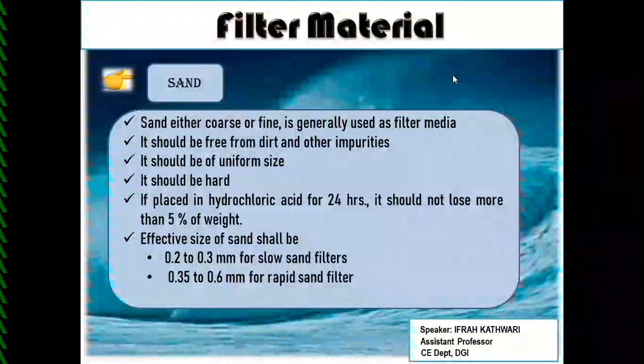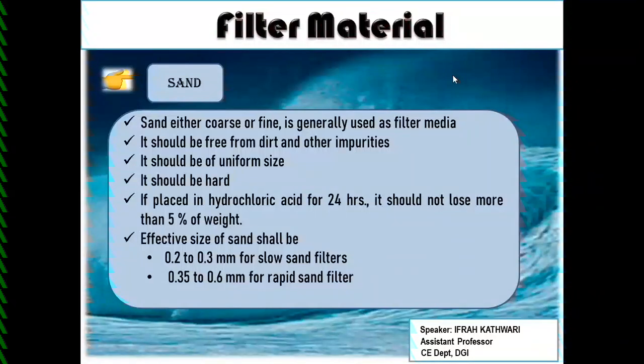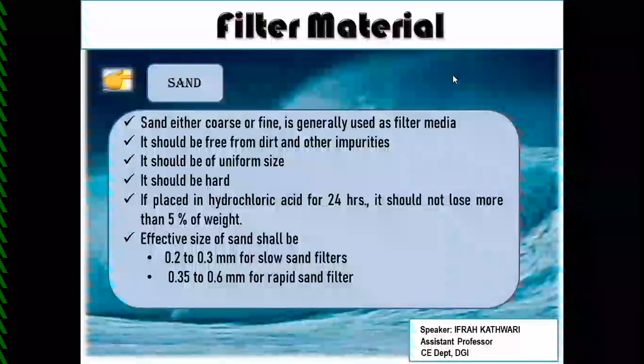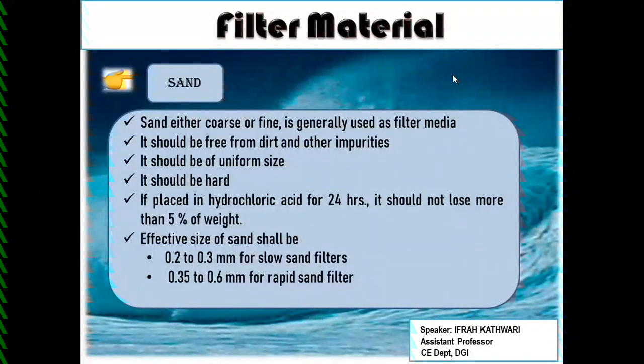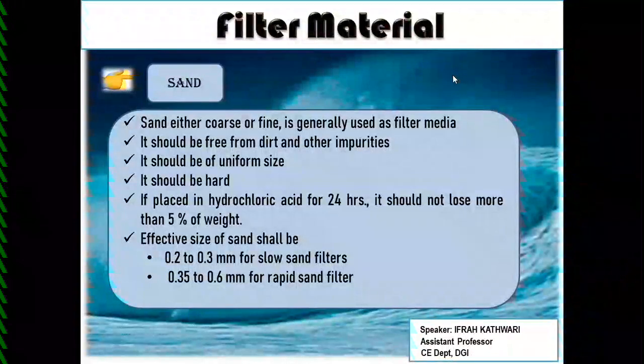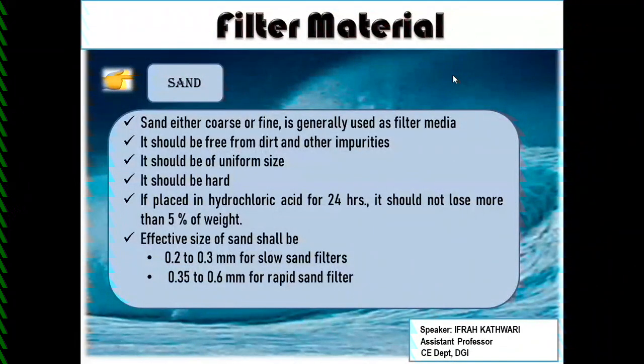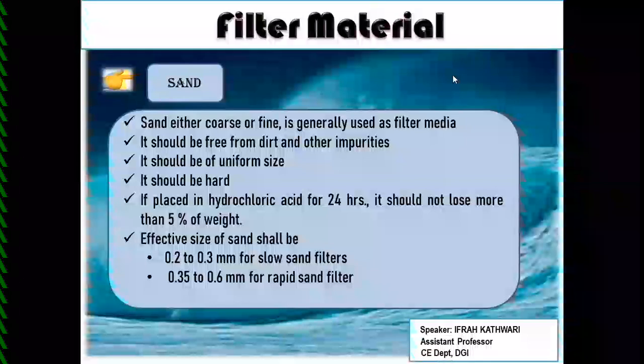So the specifications that we have to go for with sand are, firstly, it should be free from dirt and free from impurities. Then it should be uniform in size; each and every grain should be uniform in size. Then it should be hard enough, because whenever water flows into the filter media, it may get disturbed due to the pressure head or any disturbance. So it has to be hard and strong enough.